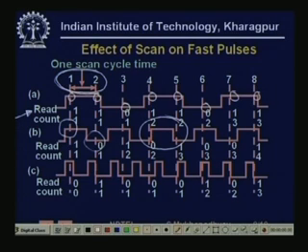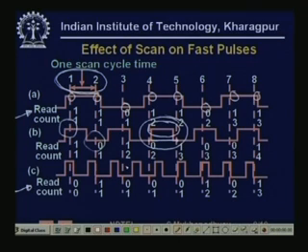So you see that the program scanned for this pulse, and when the program scanned it the value was 0, and when the program scanned it next the value was again 0. And so the program assumed that it remained 0. So that it went up to 1 in between and came down, the program will be unaware of that, and therefore there will perhaps be a small delay in the computation of the speed. If you have faster pulses coming out, still faster, then many such pulses will be missed. For example, this one, this one, this one.